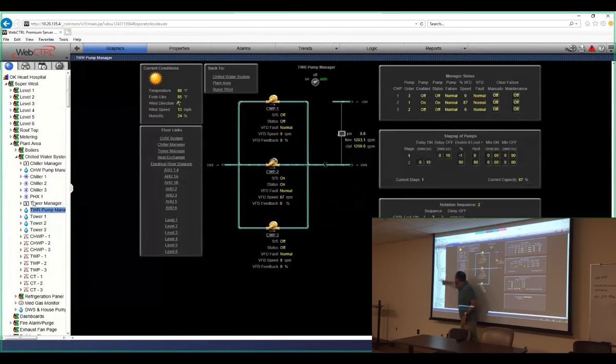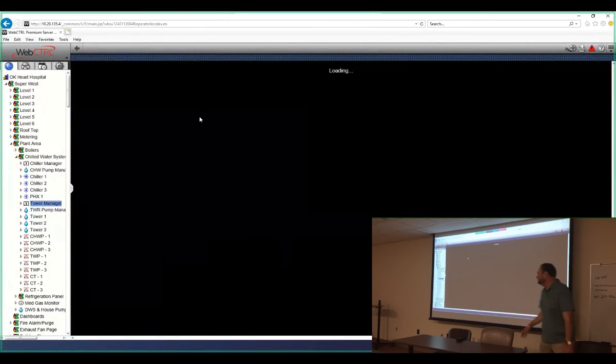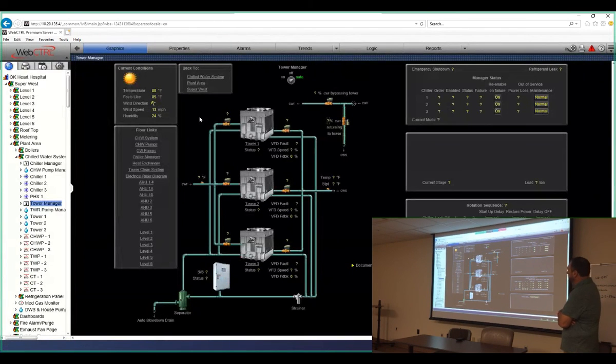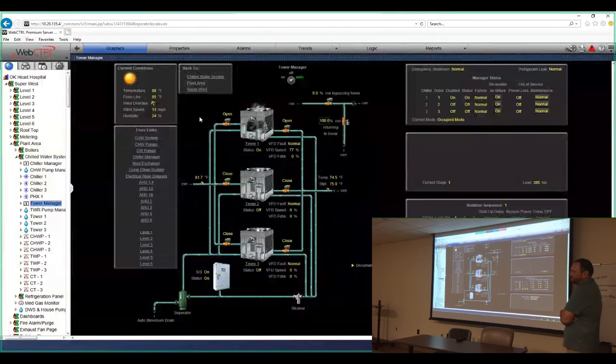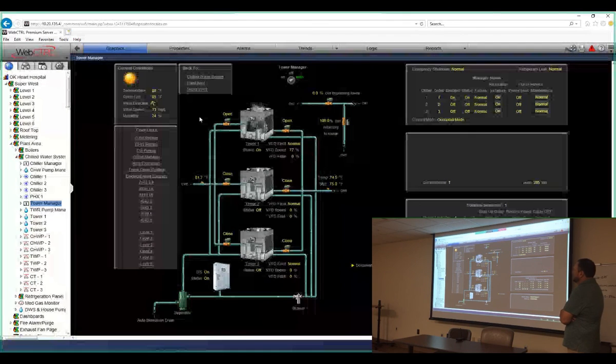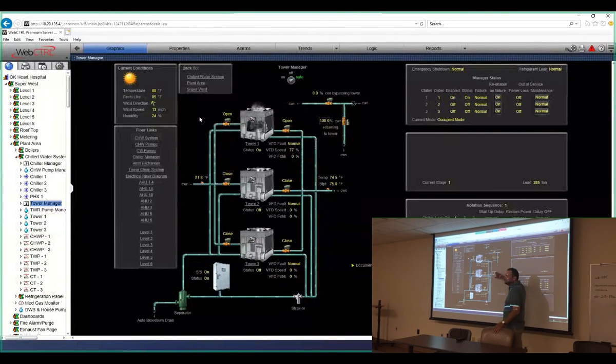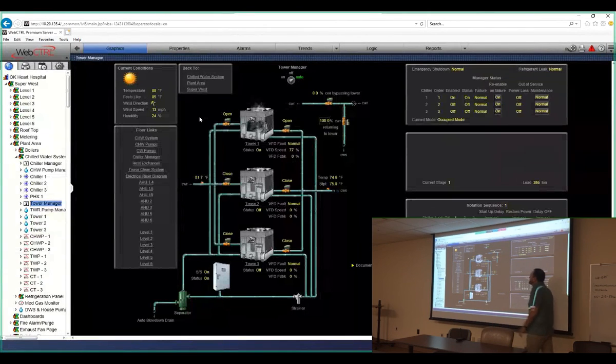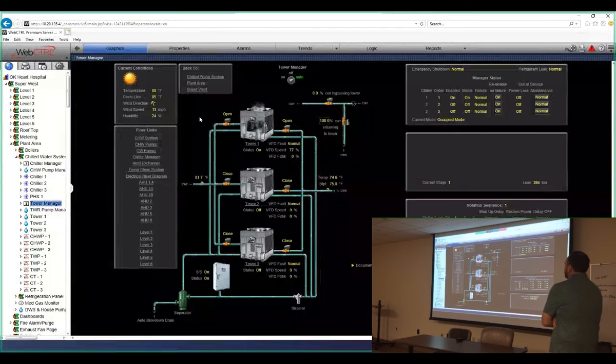Over here to tower manager. Your cooling towers rotate the same way. You can rotate them daily, weekly, monthly, and choose which ones to turn on and off, and this is what the graphic looks like. Right now, we're trying to maintain a condenser water set point of 75 degrees. Generally, it's controlled pretty well, though we reach into the 90s. Don't be surprised if this temperature goes up. With the fans running 100%, we may only be kicking out 82 degree condenser water back to the chiller, but it's running full speed. Chillers can run with 82 degree condenser water, that's not a problem, but we're trying to maintain 75. A little bit cooler water than 85 makes the machine more efficient.